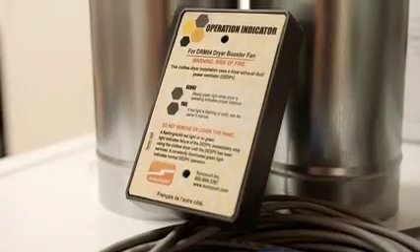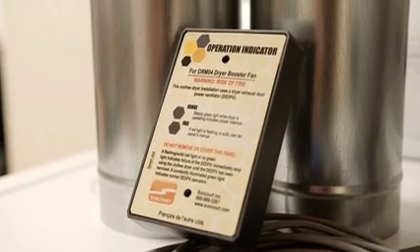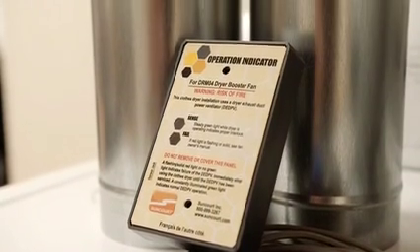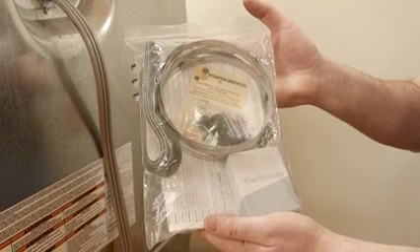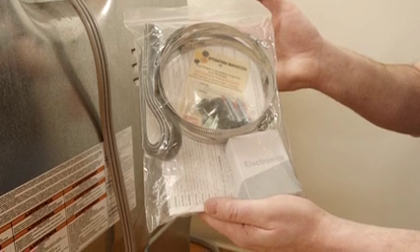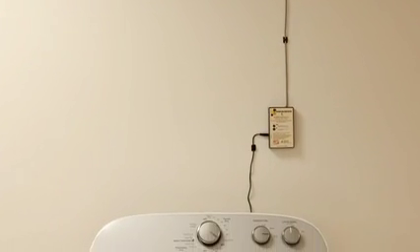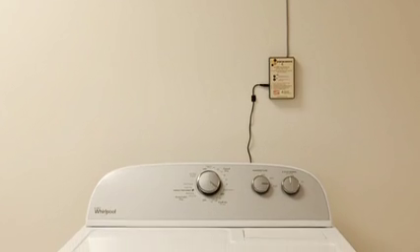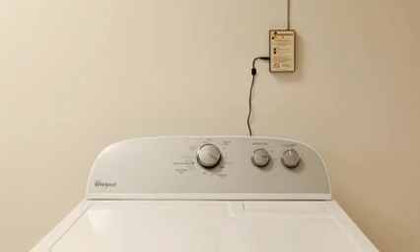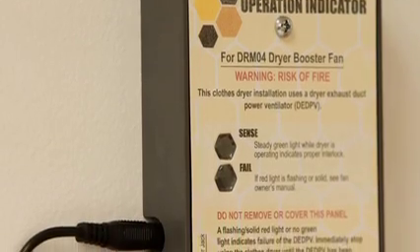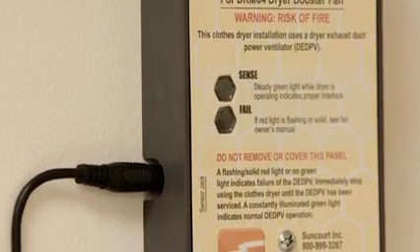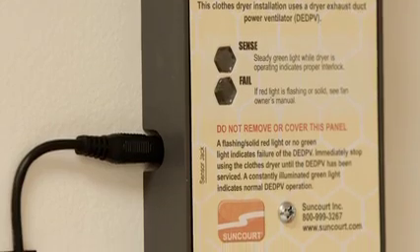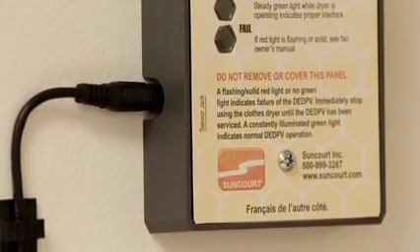Once the fan is in place, it's time to install the remote indicator. The DRM04 ships with the control wiring connected to both the ventilator and the remote indicator. The remote indicator can be flush mounted or mounted to an electrical box. The correct orientation for the indicator panel is with the remote sensor input towards the lower left side.